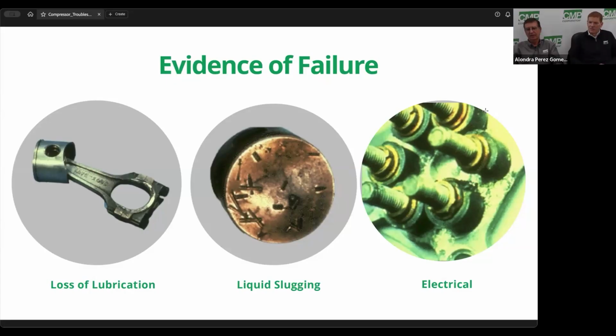Awesome. So what are a few more things that you could put on that checklist for them when they're building the checklist? So pressures, temperatures, I would say. Suction, cleaning the evaporator and the condenser. Making sure, if it's on a walk-in freezer or any kind of little freezer, that your evaporator fans are not running all the time. Most of the time they're set on what they call a defrost termination switch. If your evaporator fans on a freezer are running all the time, then when you start that freezer up, you're making the compressor act like an air conditioning compressor. It's going to overamp. It will be over its full load amp draw.